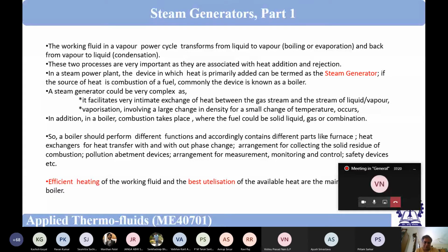So let me come back to the point which I was discussing, that what is a safety device. At least one safety device, let me tell you. The steam is being generated, but water supply is not there, so boiler temperature is increasing. There is a plug in the boiler called a fuse plug, which is made of low melting alloy.